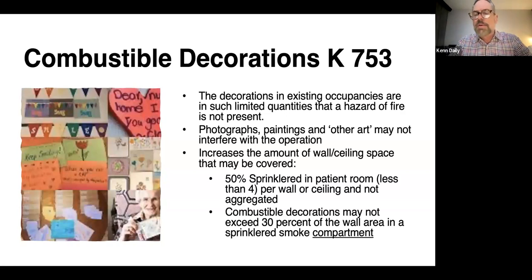Combustible decorations, again, though they were fully sprinkled, most of this shouldn't be a problem. You can cover the walls in a resident room up to 50% of the wall covered, including the ceiling, can have combustible material of like art or a bulletin board or whatever they want to attach to the wall. I've not seen many sites on this in the country. And then the other half is that the 30% of the compartment can be covered. So yes, again, the activities gym can have something. You can hang a quilt in the lobby, again, a bulletin board, framed art, whatever, in your lobbies, in your corridors, without any problems, because again, we are fully sprinkled and we are allowed to have combustible things attached to the walls in most cases.